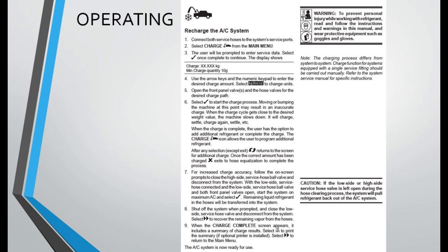Moving or bumping the machine at this point may result in an inaccurate charge. When the charge cycle gets close to the desired weight value, the machine slows down. It will charge, settle, charge again, settle, etc. When the charge is complete, the user has the option to add additional refrigerant or complete the charge. The charge icon allows the user to program additional refrigerant. After any selection, except exit, returns to the screen for additional charge. Once the correct amount has been charged, exit to hose equalization to complete the process.